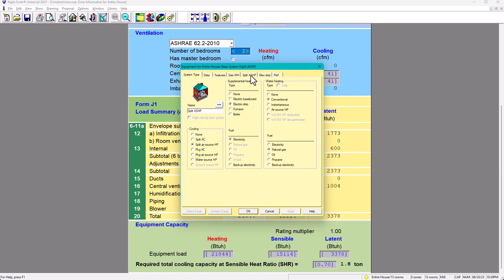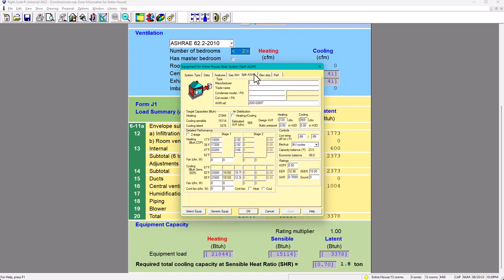And then when you go to the split air source heat pump, in here, we're going to put heating equals cooling. And then you're going to be able to find in here your target CFM, okay? So in order to do that, you can always change this number when you press F8. See in here, F8, you highlight it, and then you hit apply. See, F8. This is the default target CFM. For my building based on the 1.8 ton unit, you need at least 569 CFM.